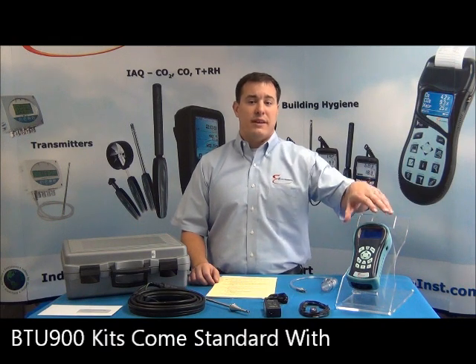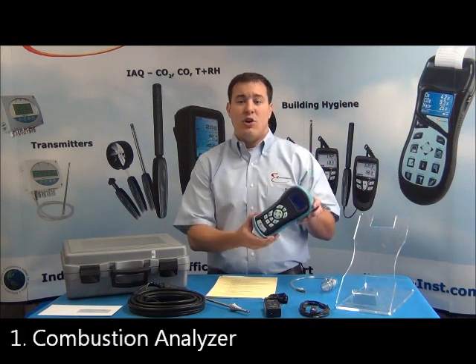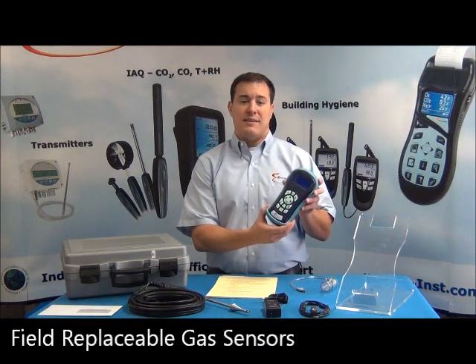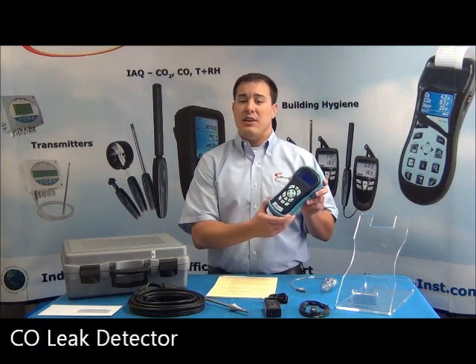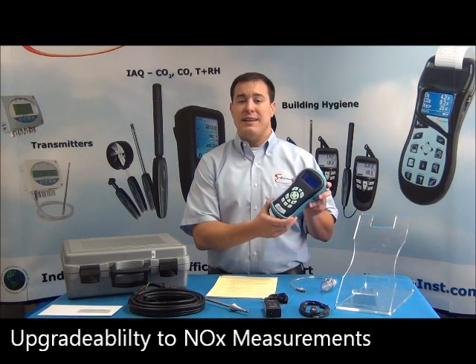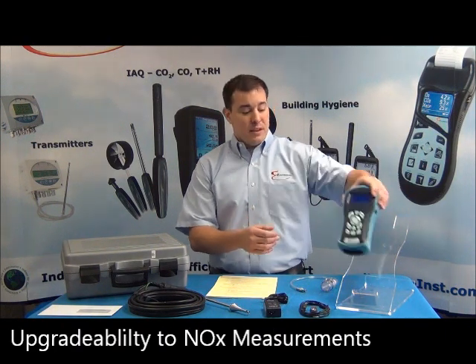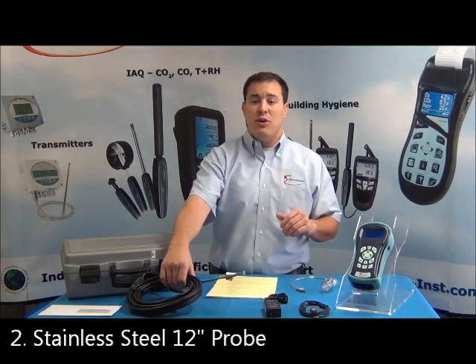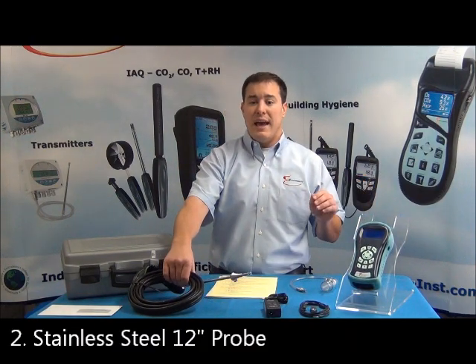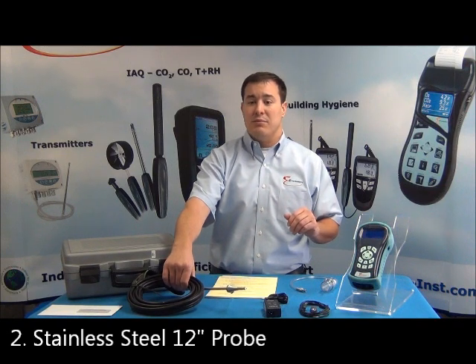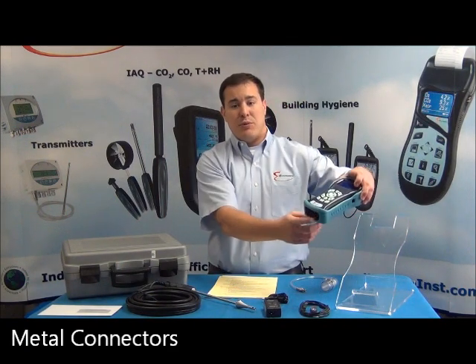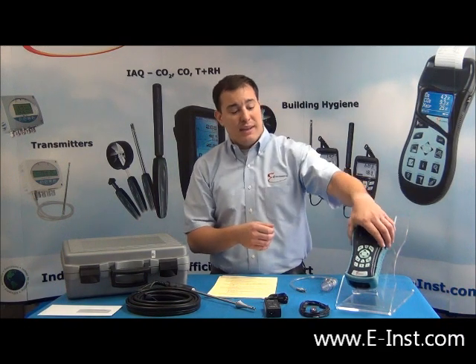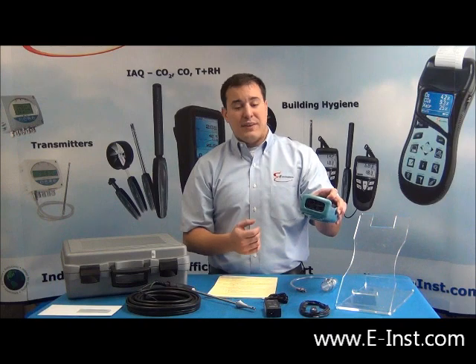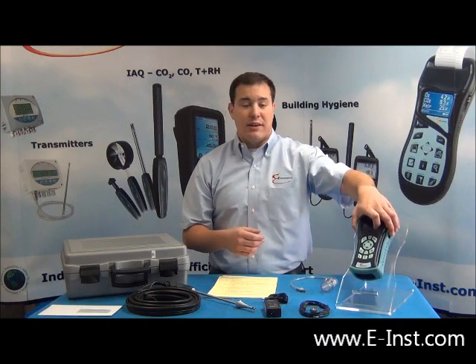All of the BTU900 kits and models come standard with the combustion analyzer, with all of your field replaceable and pre-calibrated gas sensors, built-in pressure manometer, CO leak detector, high efficiency capabilities, and upgradability to NOx measurements. They also come with the stainless steel 12-inch probe, with a dual hose assembly allowing you to take gas, draft, and temperature measurements all at the same time. You will notice we use metal connectors on both the unit and the hoses, preventing them from breaking off, which is common with other plastic connections. We also use female adapters at the bottom of the analyzer to make sure that nothing sticks out. If it sticks out, someone will find a way to break it off.